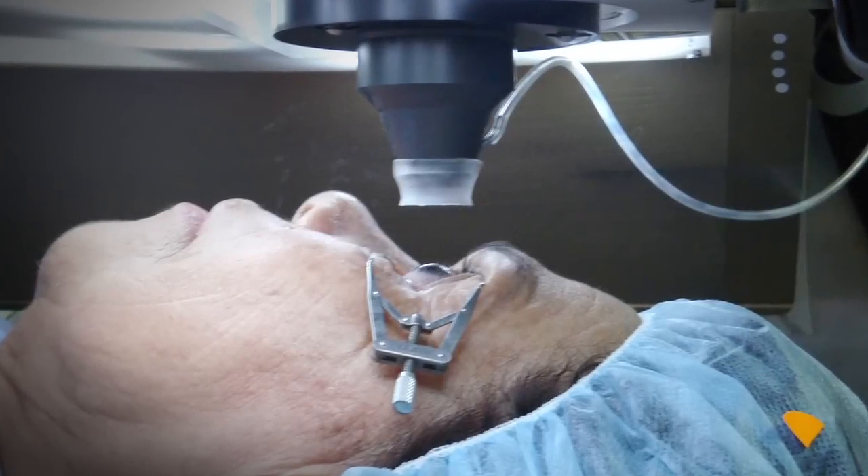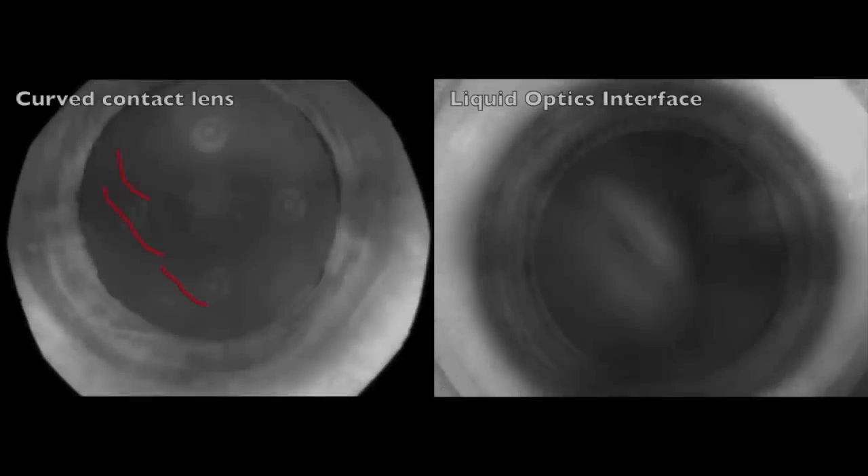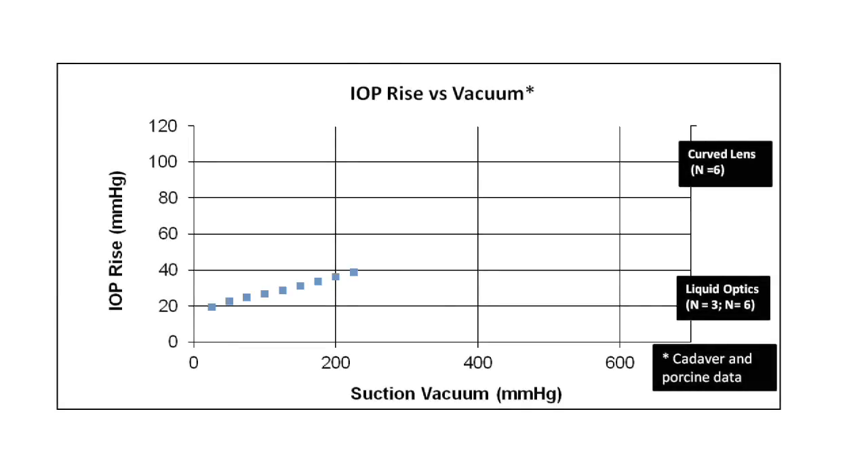OptiMedica initially used a curved applanation interface, but determined that it did not deliver the optical quality required for precision laser treatment of the lens. What we found was the curved contact interface actually deformed the posterior cornea and caused posterior corneal folds. Relative to the initial curved lens design, liquid optics showed more than a four-fold reduction in intraocular pressure rise in porcine and cadaver studies.